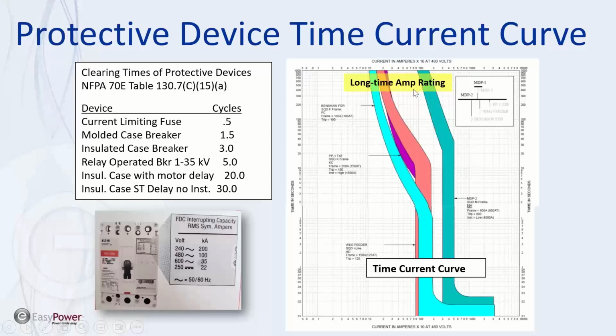This section of the time current curve is your long time. So this is time in seconds. It starts at 0 and goes up to 10,000 seconds. So this is a long time blowing. Then you go into the time delay section, which varies if you've got motor loads and things like that, so you want to make sure it's coordinated to whatever you're working with and coordinated with each other, but we'll talk about that in a second. And then there's short time pickup, and this gets into overload, and then this is short time delay down here.